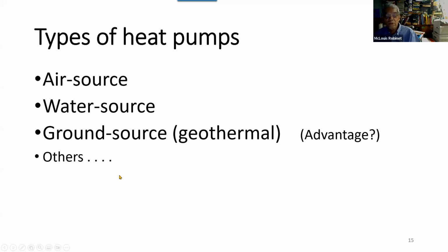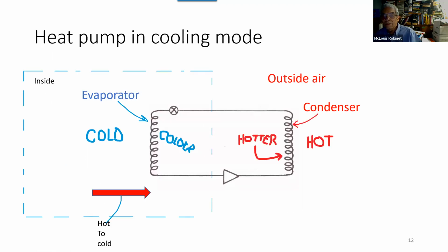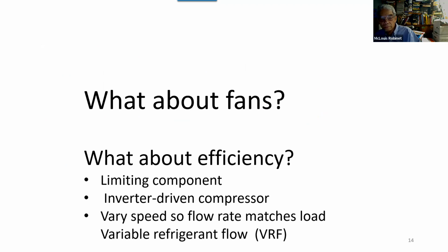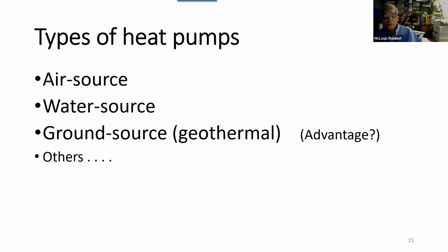So, three major types of heat pumps. Going back a bit, as you recall, we're talking about extracting heat from the outside air, from this sea of energy. So we would call these air source heat pumps, because this is the source we're getting this thermal energy from. If we were using water, we would call it a water source heat pump. If we were extracting the heat from the ground, we call it a ground source heat pump. Also called a geothermal system.